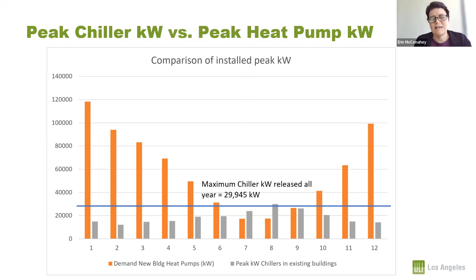And you might worry, oh, well, those orange lines are shooting up over that 30 megawatt line. If we go to the next slide, what you can see is that actually those are a very small proportion of the hours. And what we actually know is that most heating plants are oversized in Southern California by somewhere between 50% to 100%, because of the allowances that Title 24 has historically given to design teams to intentionally oversize by at least 40% for ramp up in the morning. So with better controls, it's very likely that the replacement heat pump capacity for heating is likely to be somewhere between 50% and 75% of what's there now. And so the peak kilowattage would accordingly be reduced.